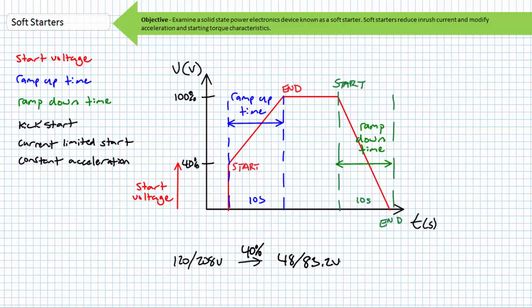A current limited start sets a user adjustable limit to current during the ramp-up time. If during the course of the voltage ramp-up, the soft starter hits this upper current limit, it lets off the gas to keep current below the ceiling. This could be used to establish a predictable maximum current draw for variable applied loads at starting.